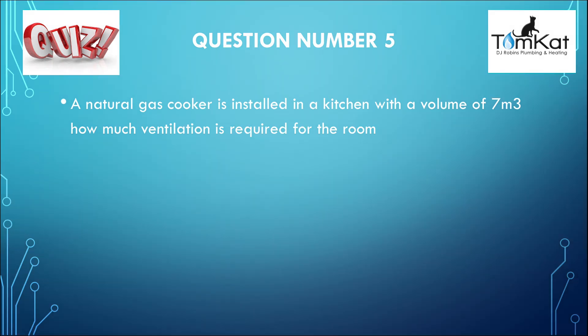Now how are we doing? Have we got four out of four so far? Well let's look at question number five: a natural gas cooker is installed in a kitchen with a volume of 7 metres cubed — how much ventilation is required for the room? The answer is B — 50 centimetres squared. That is the answer for question number five.